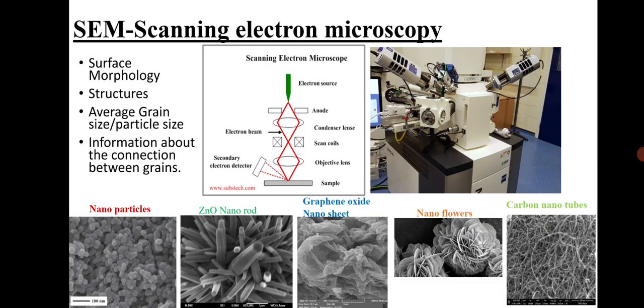The next technique is scanning electron microscopy. This is most important for people working with powder, bulk material, and thin film technology. For those working at the nanoscale and quantum dot scale, TEM — transmission electron microscopy — is most important, and I will discuss it in the next session. Coming to scanning electron microscopy: there is an electron gun which produces the electron beam, then an anode arrangement, and a condenser lens which converges the electron beam to a particular area. Then there is a scanning coil and objective lens, which are controlled by magnetic as well as electrostatic fields, and then a sample holder.